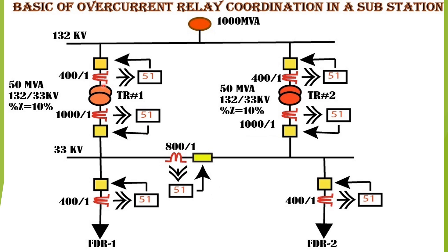The CT positions are shown from the HV side to the LV side of the transformer, and for the bus coupler CT and feeder CTs. The CT ratio for the HV side of the transformer is 400 by 1, for the LV side it is 1000 by 1, for the bus coupler it is 800 by 1, and for each feeder it is 400 by 1. Overcurrent relays are connected from the CT secondary side of the feeder, bus coupler CT, LV side CT, and HV side CT.